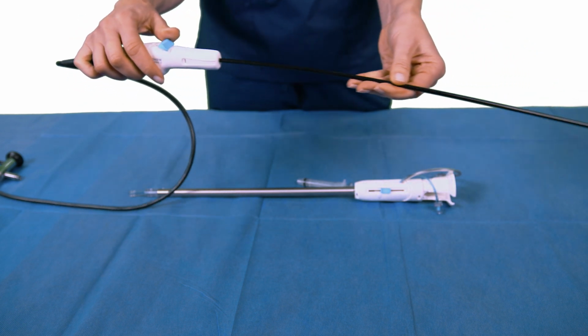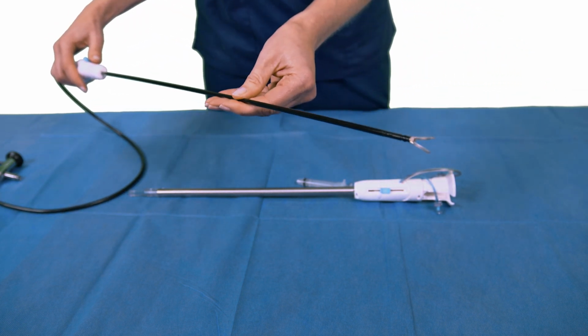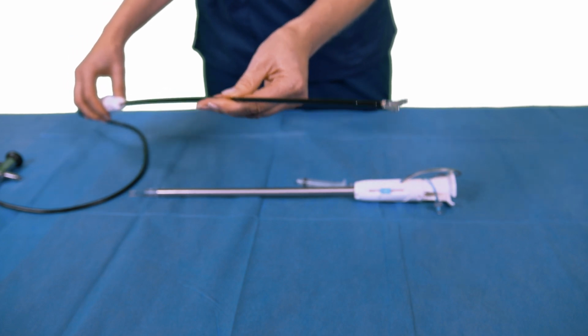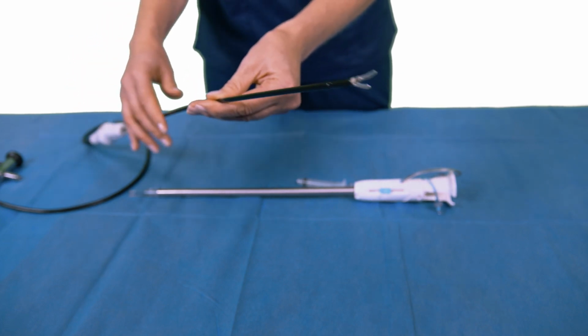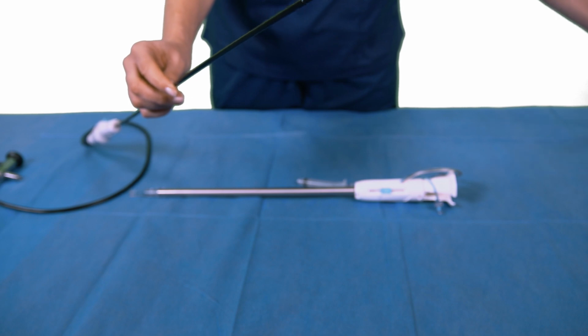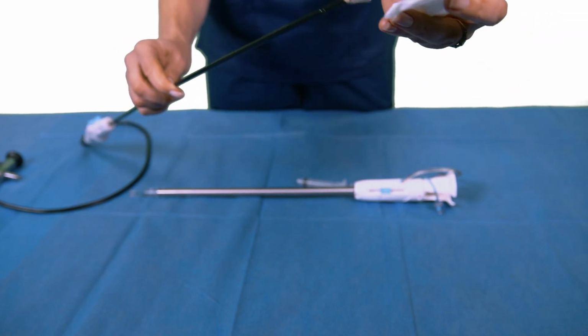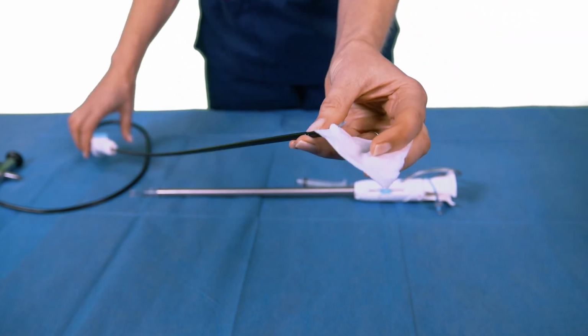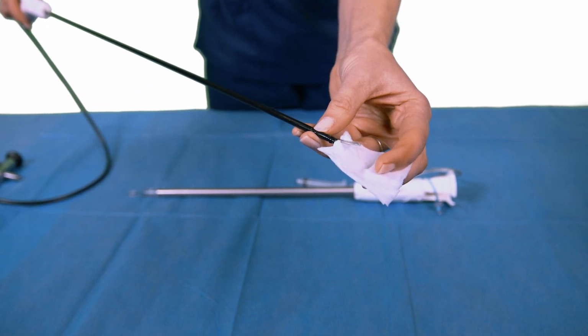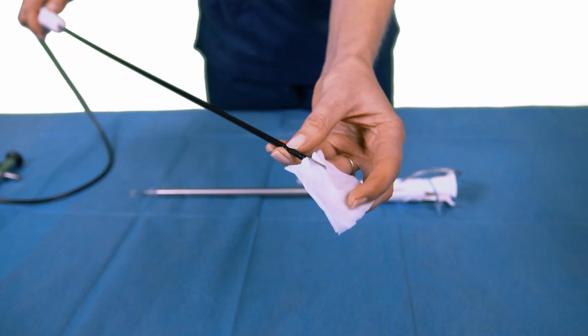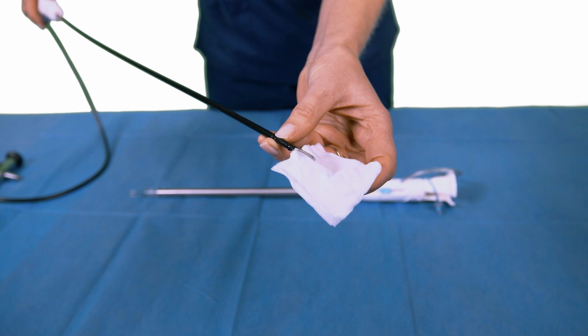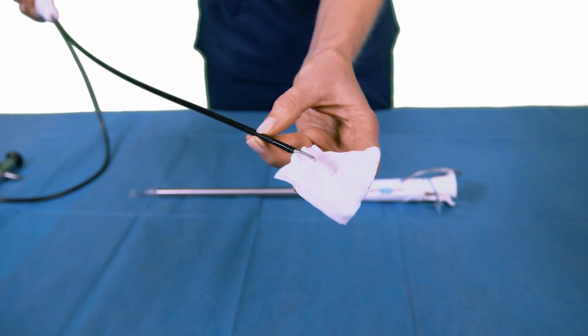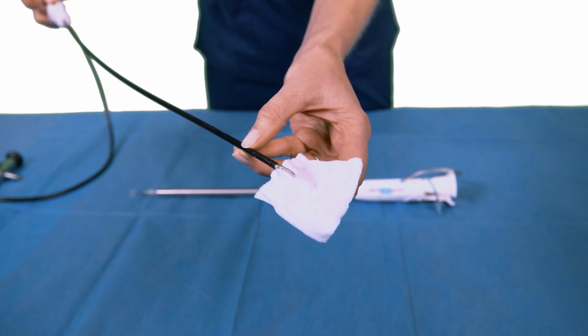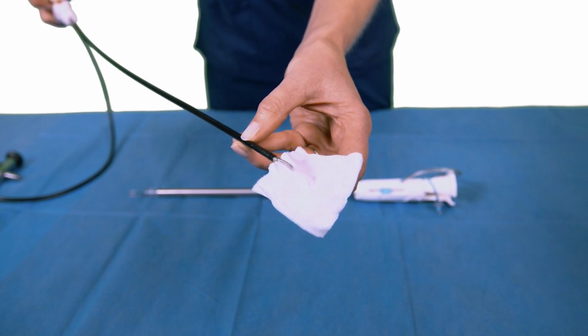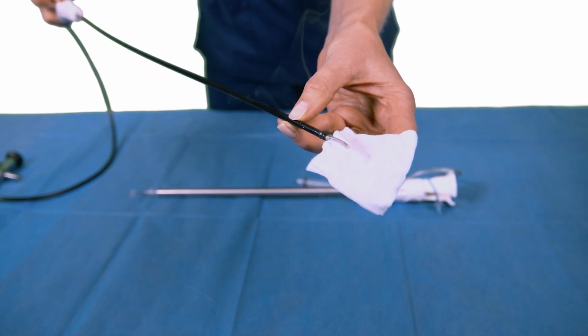Prior to using this in a case, you should test that the circuit is complete. To do so, you would take a sterile, moistened gauze and place it within the jaws. Close the jaws by pulling the toggle back, and then pull all the way back to activate the jaws. At this time, steam should be generated. That indicates there's a complete circuit.